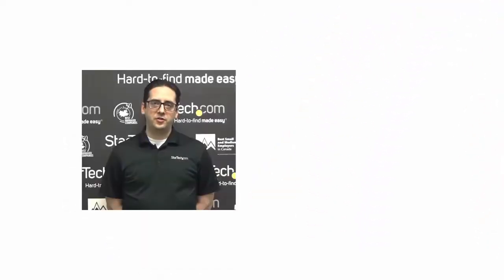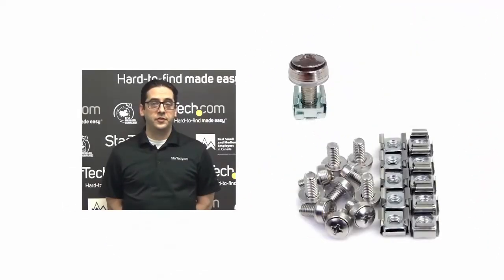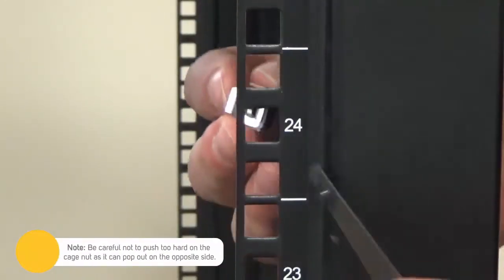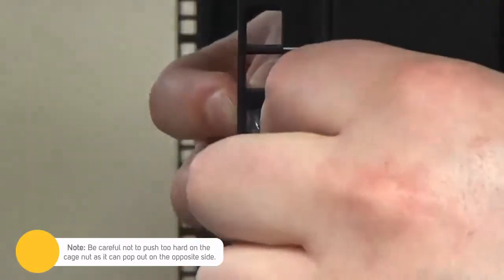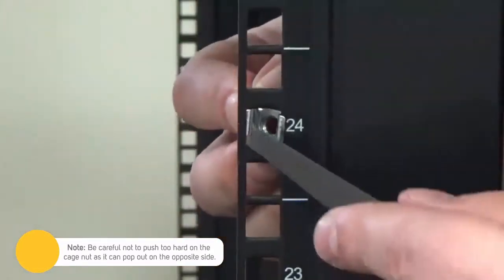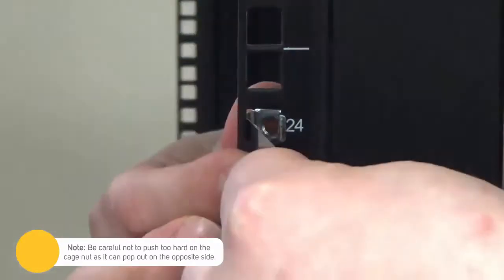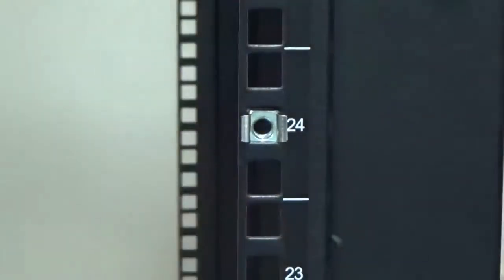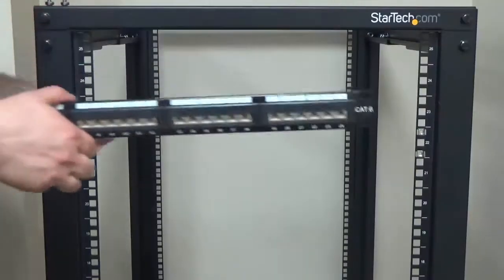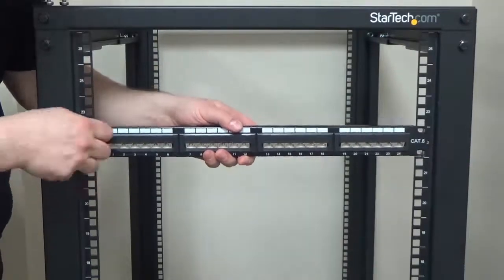We'll be mounting the patch panel using cage nuts, so the first step is to install them. To install a cage nut, use your tool to attach one of the wings from the cage nut. Keep the pressure on the cage nut with your finger, and then attach the other wing. Once installed, we can use the cage nuts to mount our patch panel.